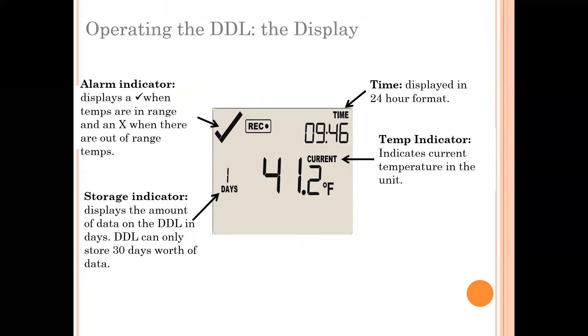The day count is how long the DDL has been running since it was last downloaded. We require you to download the temperatures every 30 days. So if you saw, say, 28 days on there, it would be a good idea to download your temperature logs and submit them.